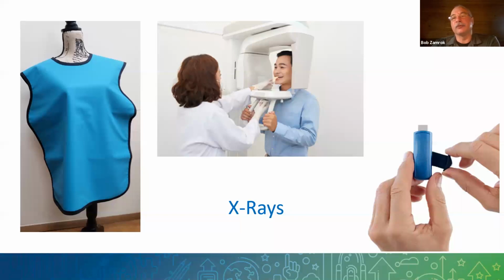and the concentrations are higher than they really should be by definition from the manufacturer. And where the thought process comes from, and I hear this from staff and offices, is if a little bit's good, a little bit more is better. It's really not. It really isn't. You're just degrading the plastic so much, and some of the metals corrode too.